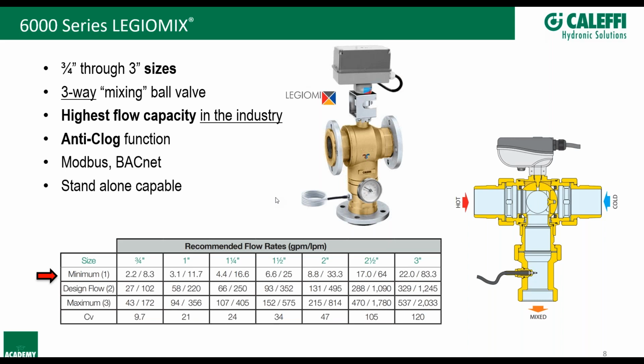That's exactly what I was talking about earlier with specific controls. I know some boilers, if they're using a resistance-based temperature sensor, you could actually use an aquastat instead. Infinite resistance or no resistance simulates really hot or really cold temperatures, so chances are you might still be able to use a bang-on, bang-off aquastat to control that temperature. I'm a very technical guy and I'm trying to dial that back, but if you want to go offline about it, I'd be happy to indulge. I don't have a very specific answer for tekmar in particular.